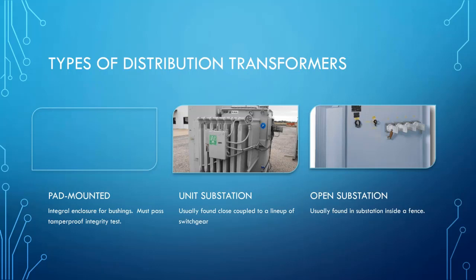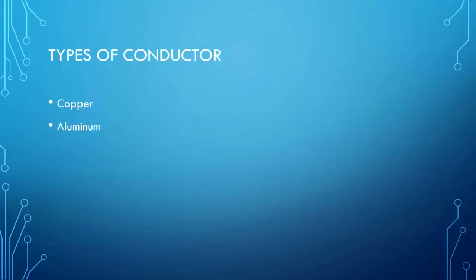So there's also a unit substation transformer, and we define these transformers as a transformer that usually is close coupled on both sides or one or more sides to a piece of switchgear. And usually the bushings are enclosed so they are not exposed to personnel. And finally, the open substation type unit usually has cover mounted bushings. It exists in a substation, usually a utility substation, and it has to have a fence around it.